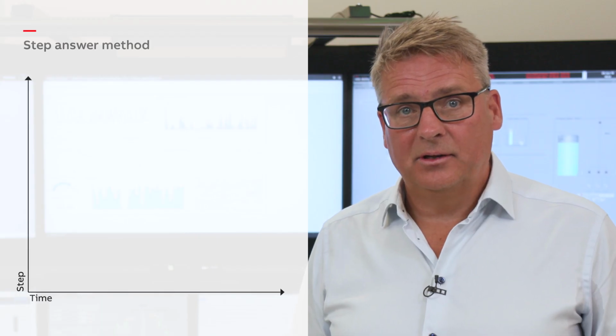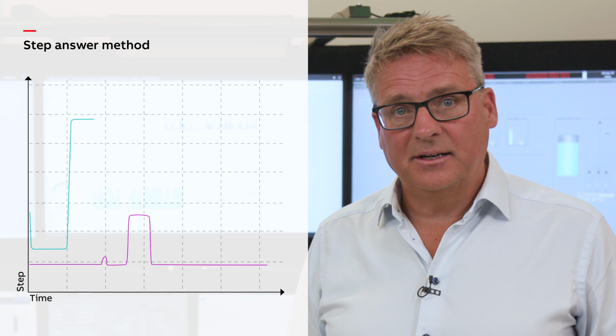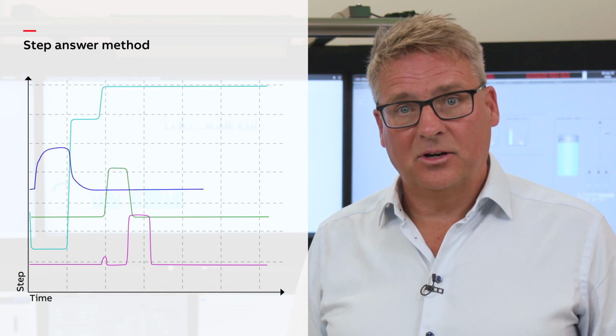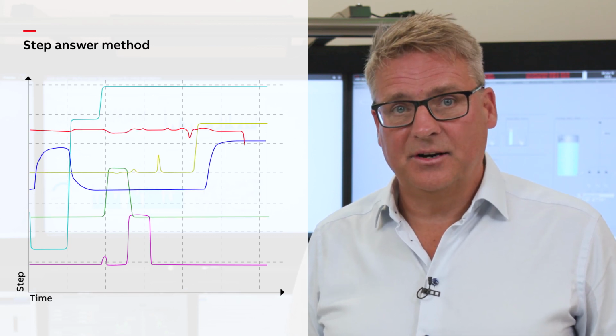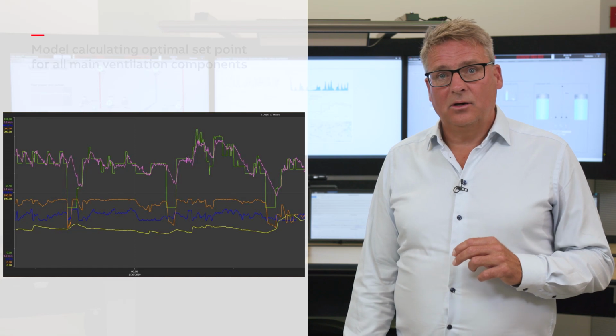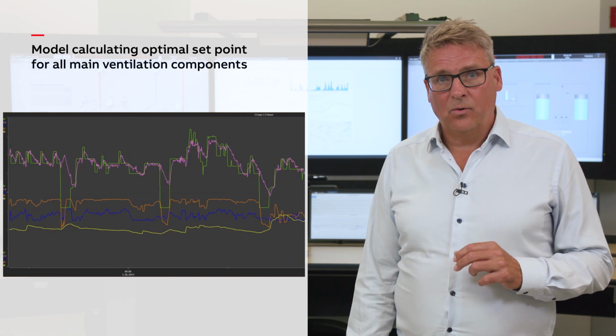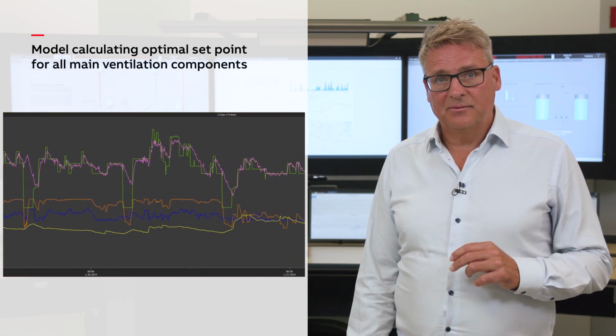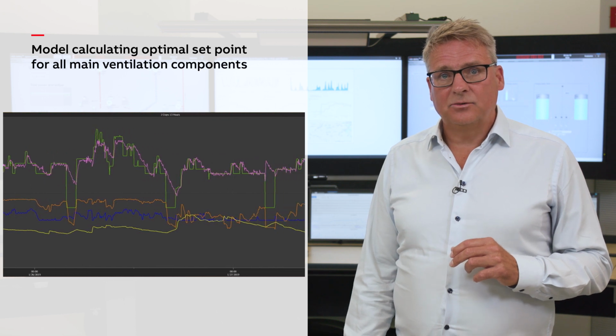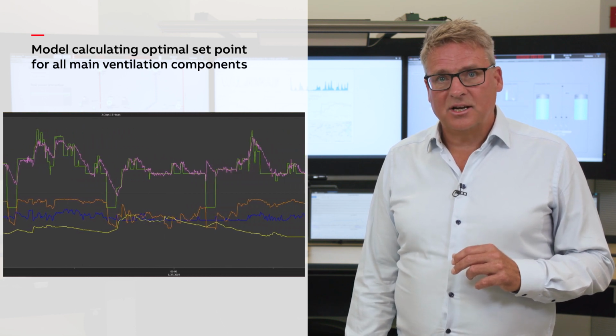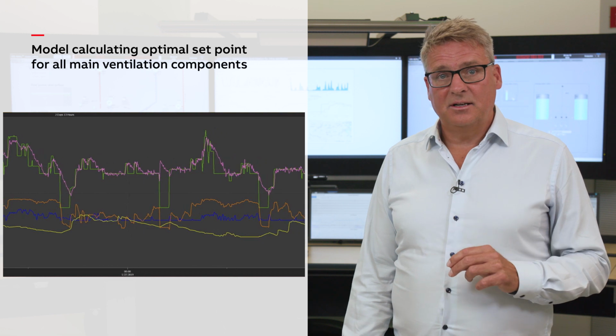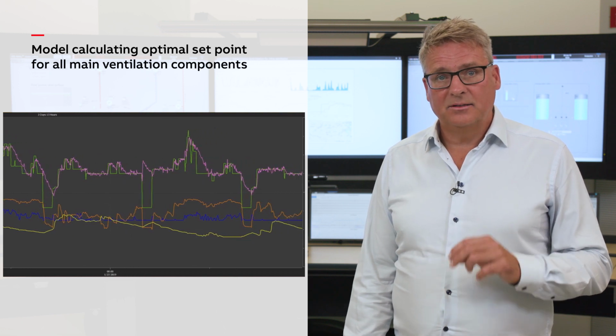The empirical model can be extracted from operation data or via a step answer method and requires minimal additional engineering and tuning. The model calculates the optimal set points for all main ventilation components for a given demand, and uses feedback control from sensors such as flow sensors, which guarantees the right amount of air is delivered.